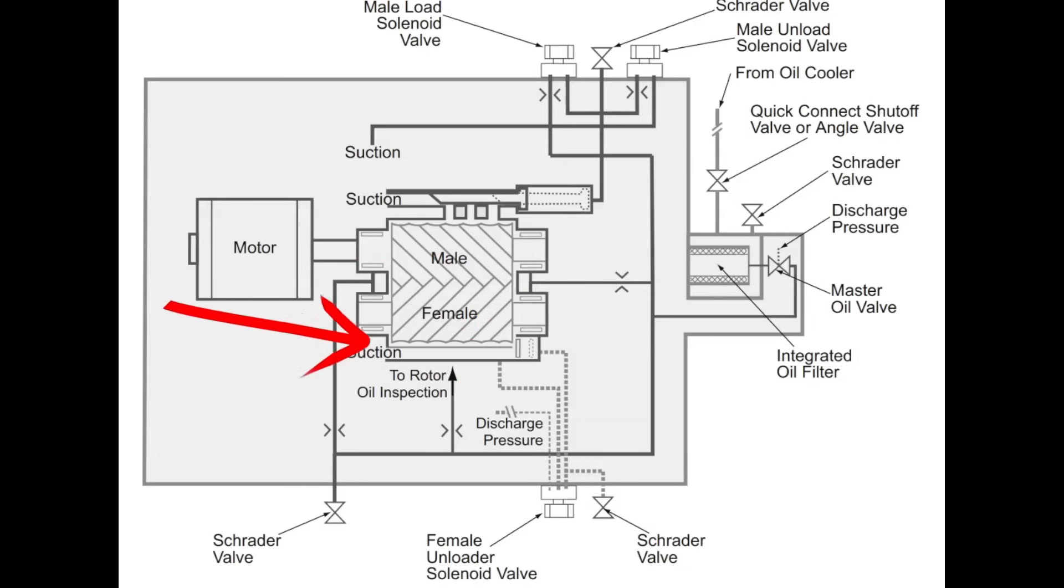So by having this bypass open here, we are reducing how much pull comes our suction gas over here. So by reducing that suction pull, it gives our metering device time to kind of catch up and get control of the superheat, while also reducing the starting current on the motor. And then once the motor comes online, we're stable for a few seconds, it doesn't take long, you'll hear this female unloader engage.